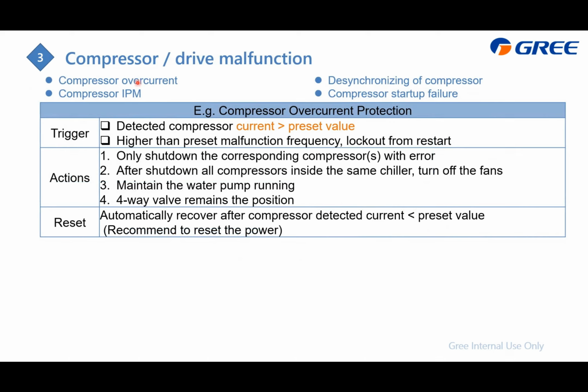And the next is the compressor or compressor drive malfunction, including compressor overcurrent, compressor IPM malfunction, desynchronization of the compressor, and compressor startup failure. Actually, this has a relationship with the current, especially when the compressor current is higher than our preset value, it will trigger this error. And here are the actions. First, shut down the compressor, and if all the compressors of the same chiller are shut down, then we turn off the fans of this chiller, and at the same time maintain the water pump operating. If in heating mode, we change the four-way valve position. And of course, this will automatically recover if the detected current is less than our preset value.